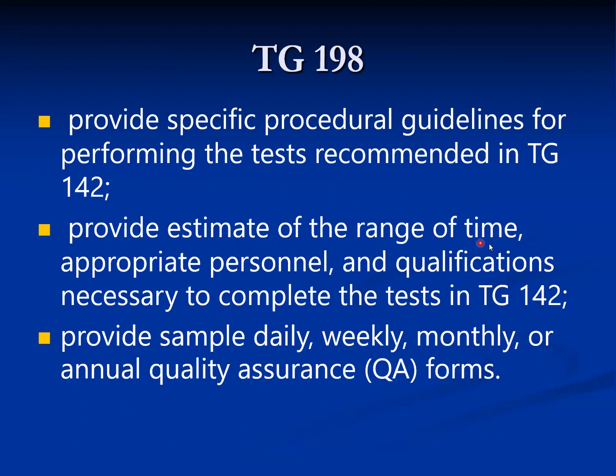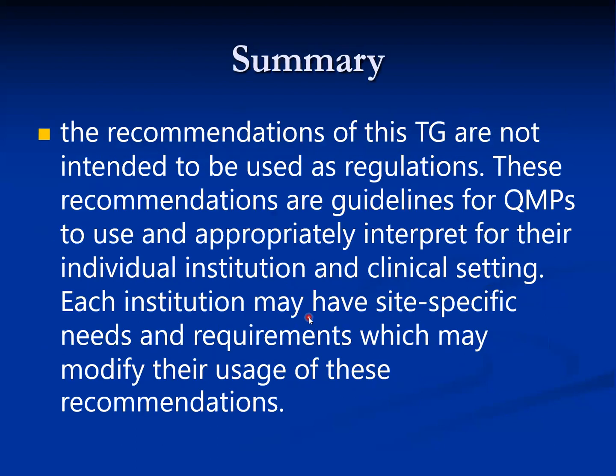TG-198 provides an estimate of the range of time and personnel qualifications necessary to complete the tests in TG-142, and provides sample daily, weekly, monthly, and annual quality assurance forms. In summary, the recommendations of these task groups are not intended to be used as regulations. They are guidelines for qualified medical physicists to interpret and apply appropriately for their individual institution and clinical settings, as each institution may have site-specific needs and requirements.